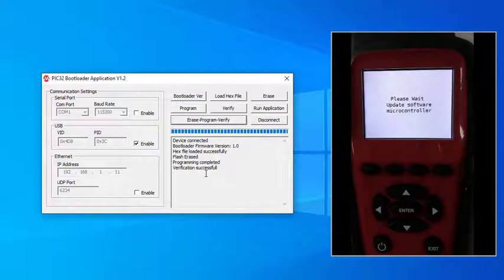Now let me talk about that verification successful message. That means that the information in the hex file that you installed is identical to the firmware and settings inside the Navigator Plus. Later on, as you use your Navigator Plus and you change settings and then you go to install a firmware update, you may see this say verification failed. That simply means that the hex file did not match the Navigator Plus firmware and settings exactly. No big deal. You can be confident that when programming completed shows, your Navigator Plus is programmed properly.